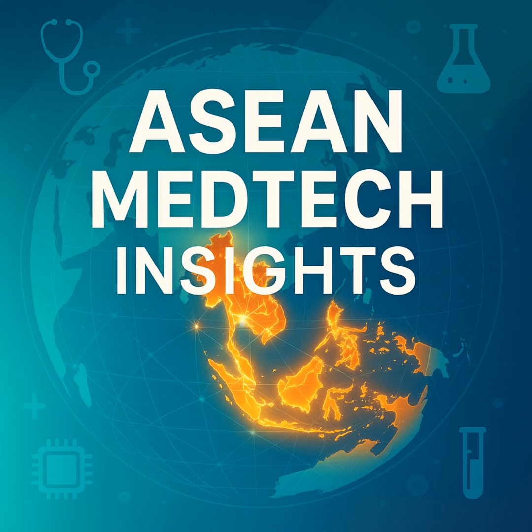A critical requirement here is the need for a local authorized representative. This entity must be based in the Philippines and is responsible for all communication with the FDA, as well as post-market surveillance obligations. This is a non-negotiable step and a common hurdle for foreign manufacturers.